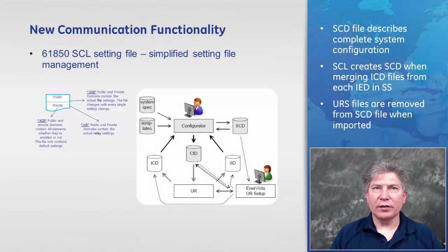The SCD file, the System Configuration Description file, describes the complete system configuration, including the single line diagram, all the IEDs and their information models, and the data flow between the IEDs. It is intended for configuration exchange from the System Configurator tool to each one of the IED Configurator tools.